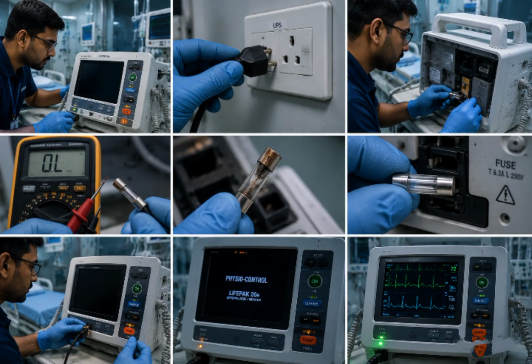The first problem which we might face is the device not powering on, which means the defibrillator is not turning on. First, check the power cable connection as given in the image. Make sure the cable is connected properly to the wall outlet. Next, check the hospital power socket. Inspect the cable for any damage. Verify the main power switch.